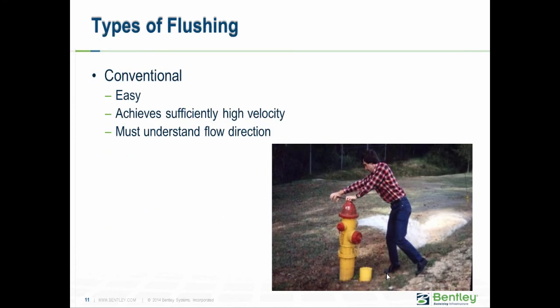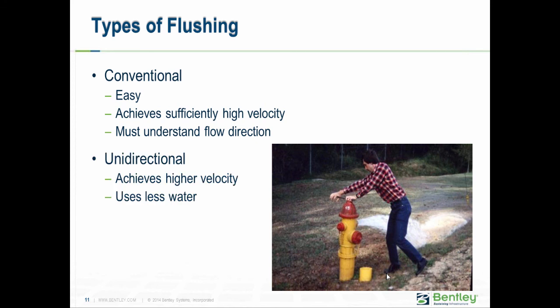The types of flushing: conventional is very easy to set up and you can get by with a minimal crew. Usually you can get a high enough velocity or quality, but you should model this ahead of time to understand the direction of flow and where you're moving the water. Unidirectional flushing takes a lot more work to set up, but uses less water and yields much higher velocities. Where you need really high velocities or precise flow direction control, unidirectional flushing can be worth the effort. My usual approach is to try conventional flushing first, and if you can't get high enough quality or velocity, then look to unidirectional flushing.